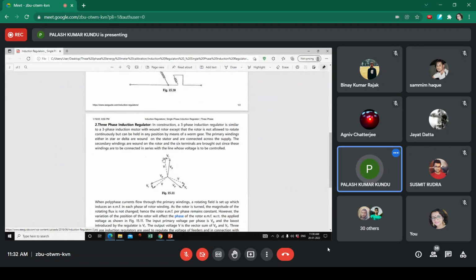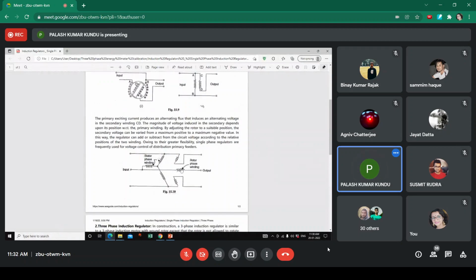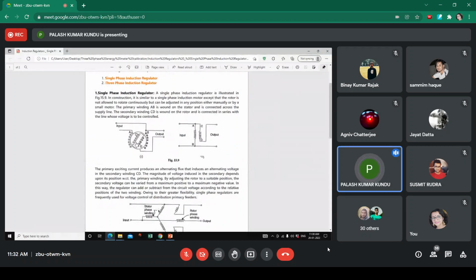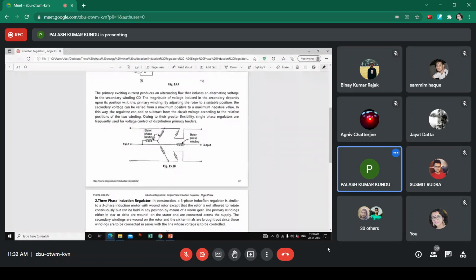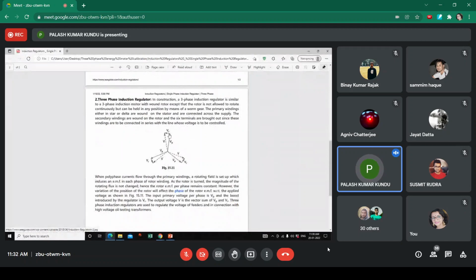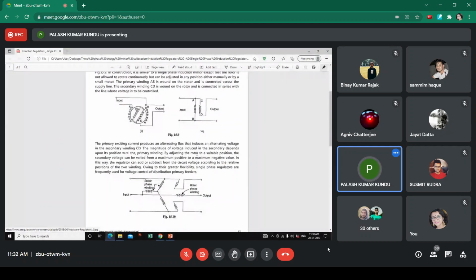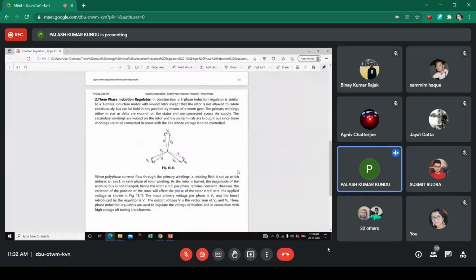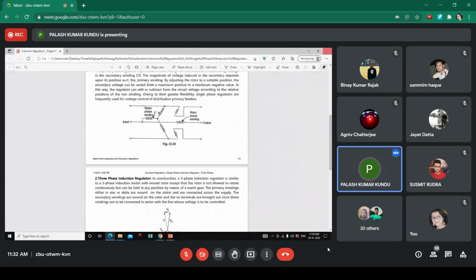But this is the voltage which will be induced according to the spatial angular position of the rotor. So the more the RMS magnitude of this rotor voltage VR, the more the phase shifting operation. And this is a balanced phase shifter, so the three-phase winding will provide the phase shifted voltage with respect to the primary input. So that is the working principle of the three-phase induction regulator type phase shifter.